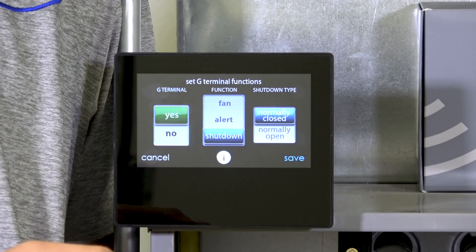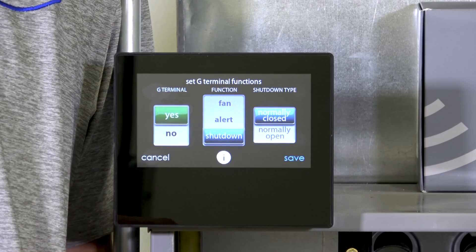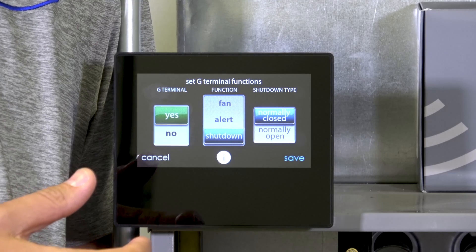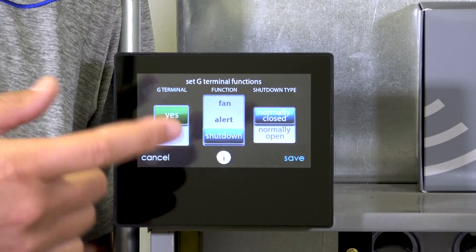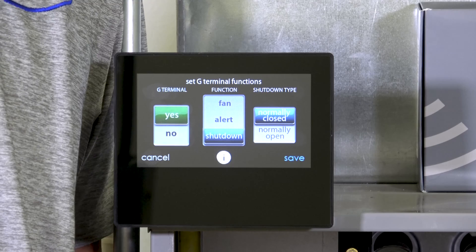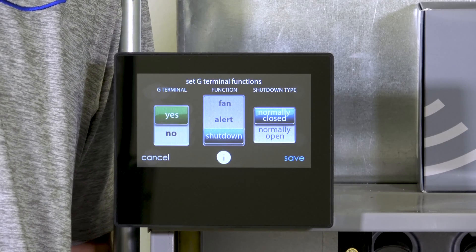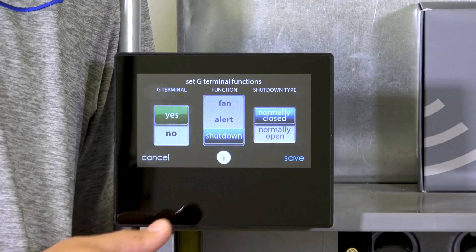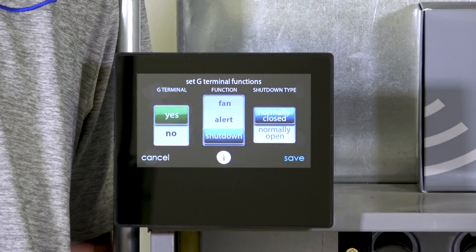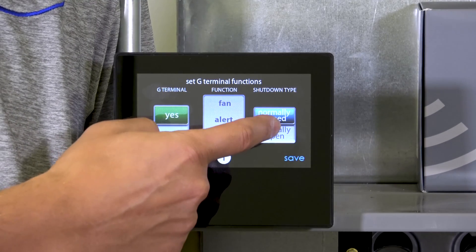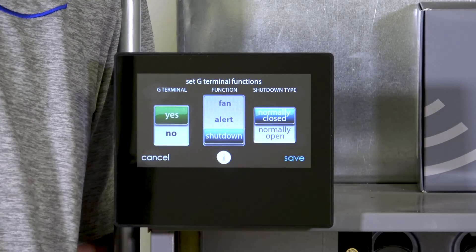There's also the opposite option: if something wires to G and R and I pick Shutdown, it'll turn off the blower and all heating and cooling and shut the whole system down. For example, you could install a duct smoke detector — required on commercial buildings at 2,000 CFM and higher, but you could use one residentially too. If it detects smoke, why would you want to keep running the blower and distribute smoke throughout the house? The smoke detector wires to the G terminal, and I can select whether it's a normally open or normally closed contact — for a smoke detector it would be normally closed.